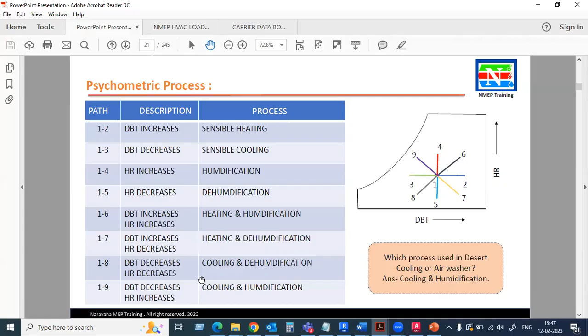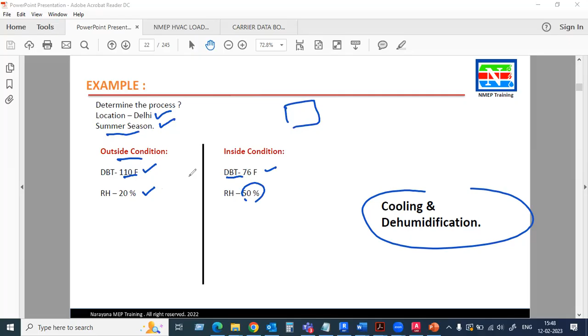Right. So what is the use of this? What we learned, we will understand with some examples. Take the example of Delhi. Just before we do all the heat load calculation, how to arrive, what process we require, what all things we require. Delhi location, summer season, outside temperature: dry bulb temperature 110 degrees Fahrenheit, relative humidity 20%, and inside the room we have to maintain dry bulb temperature 76 and relative humidity 50%. So what is the conclusion here?